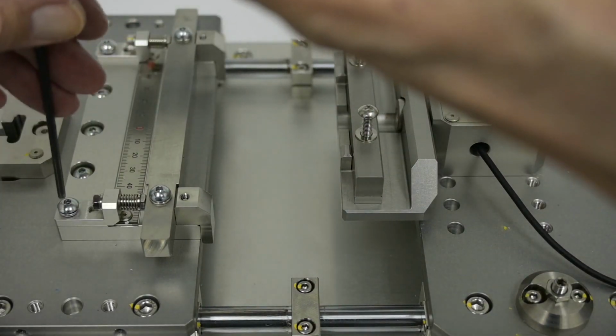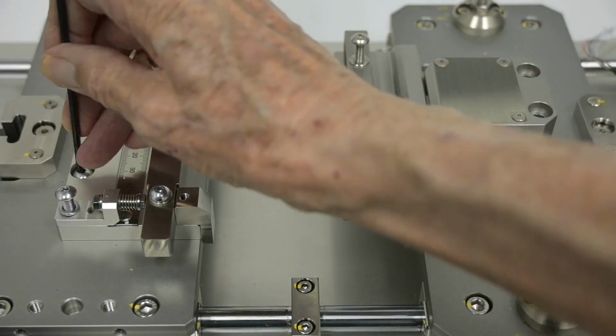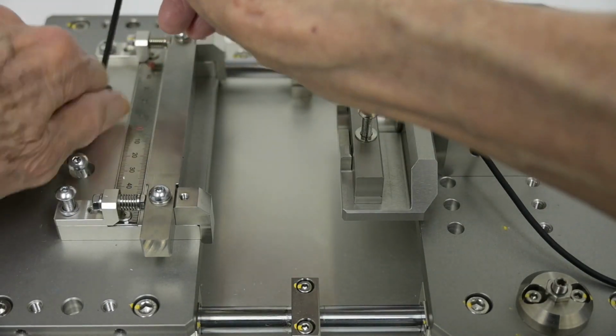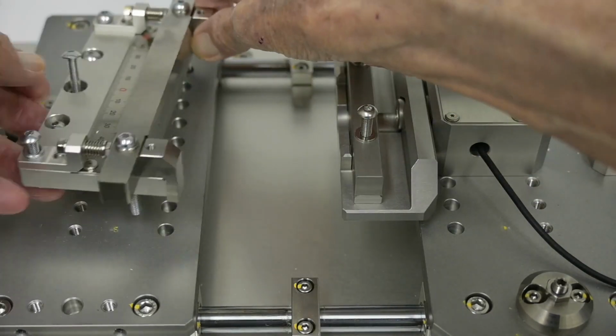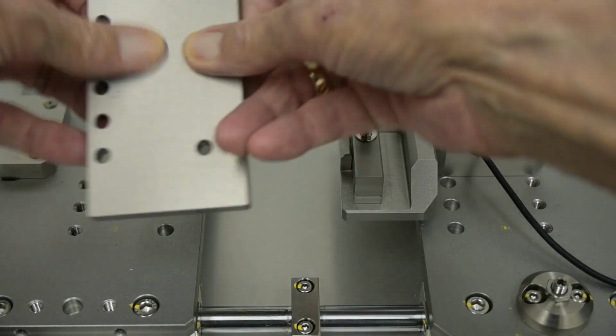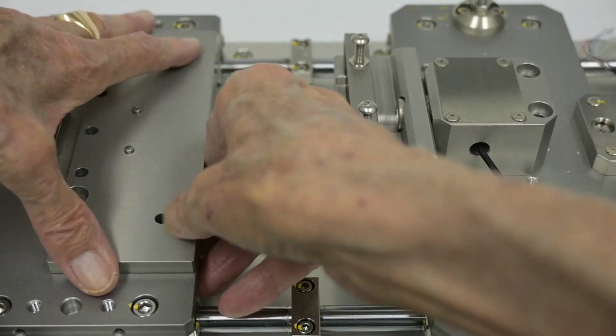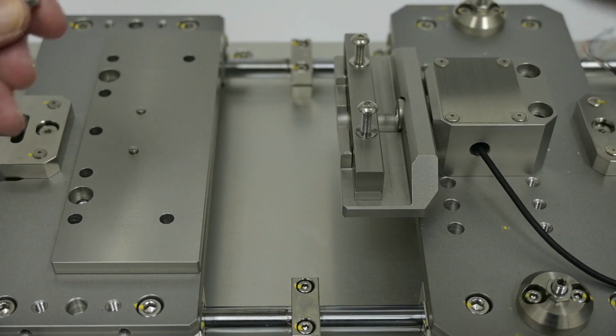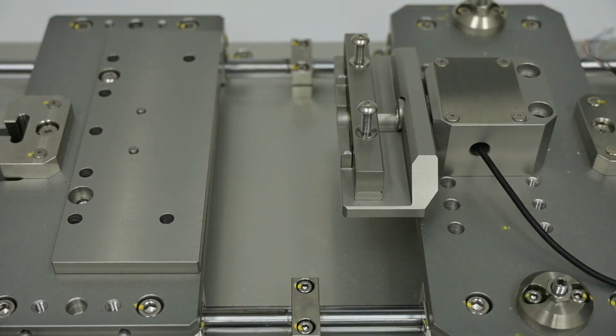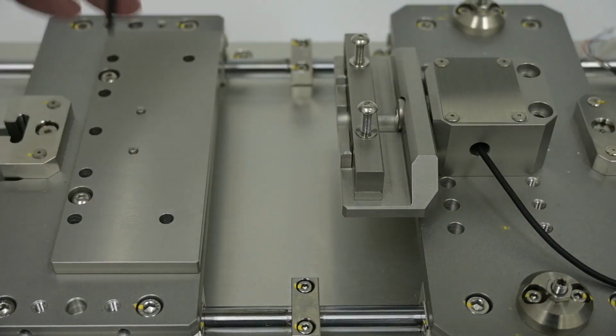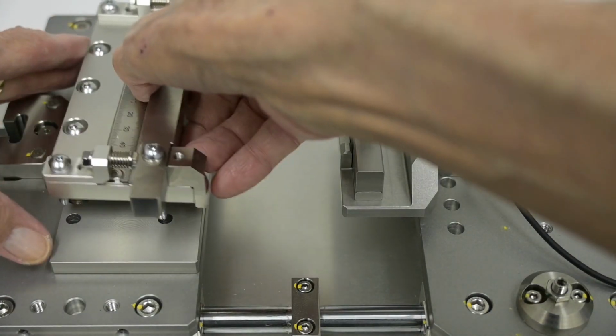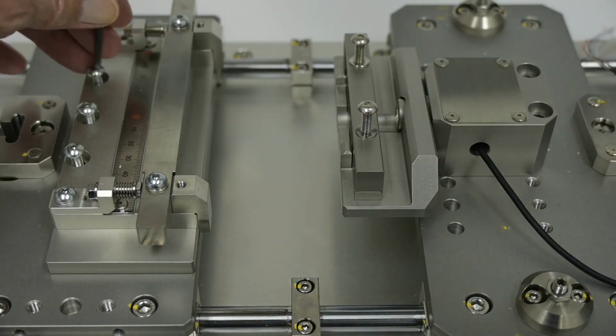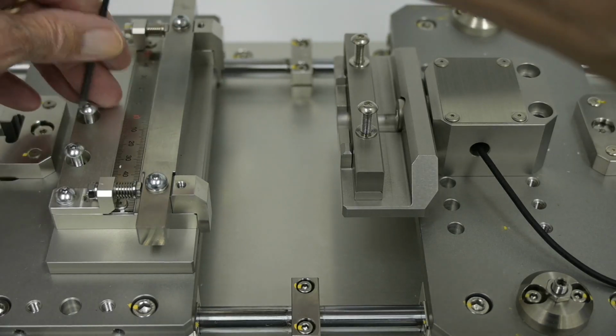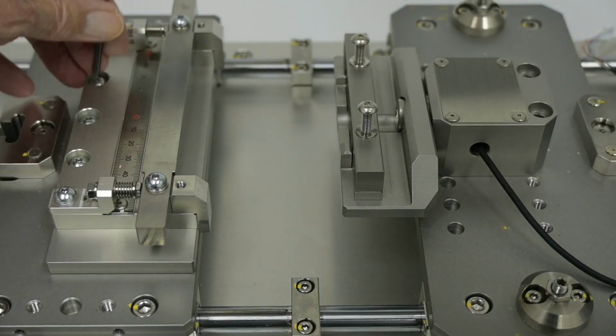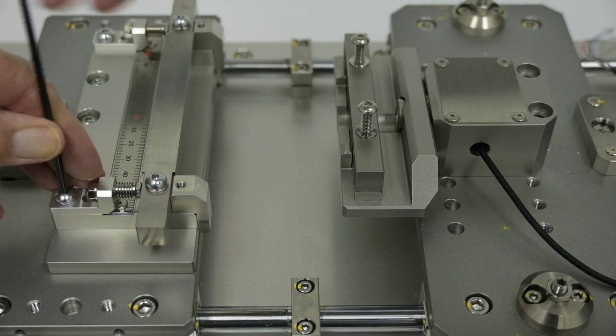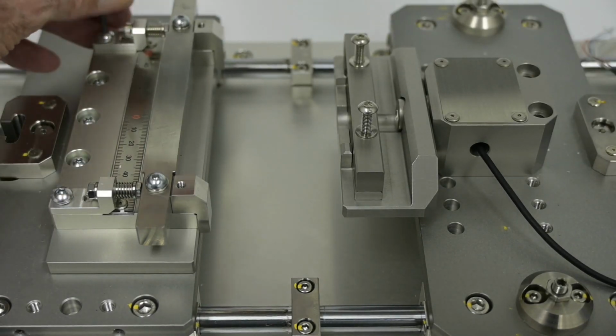Loosen the 5 screws on the moving clamp. Lift off the clamp, keeping the screws. Place the spacer in place with the holes aligned with the pins. Install the 2 screws. Put the moving clamp on top of the spacer. Tighten the 3 middle screws. The 2 outside screws are not long enough now. You can leave them loosely in the clamp or put them away for when you remove the load cell clamp.